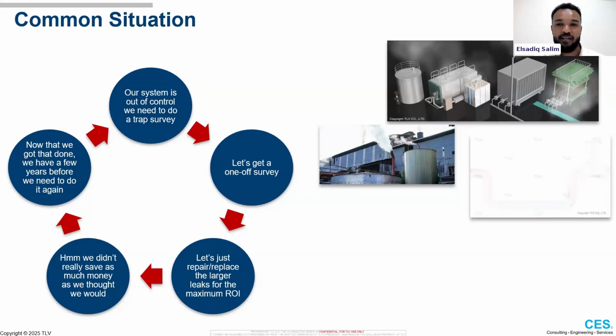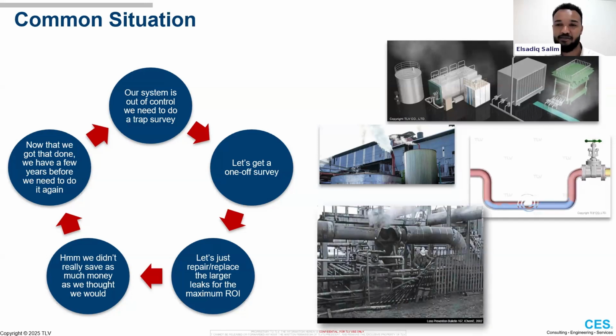But even more scary, in my opinion, are the water hammer issues, and that's if you don't manage to get that condensate out of your system from failed cold, blocked up steam traps. There's one mechanism of water hammer demonstrated there. The results can look something like this.